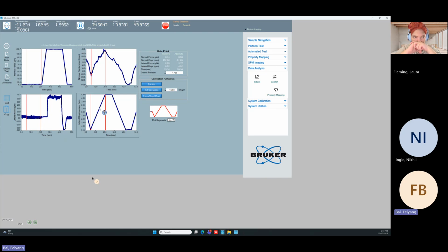So not too crack? So yeah, the reason I had this one moved in a little bit is, do you see how there's like this bump and then it goes down? I think that that's artificial and I want a better measurement. So I think that this is a more accurate representation of the sample tilt than going to the other side of this bump. So that's why I'm headed there. But yes, now you can hit tilt correction and it's going to make these 2 at the same lateral normal displacement or very close to it. So it's flattened this out. Now there is some bumps here. Aluminum is a weird sticky sample, so we're probably getting a little buildup. But you can see that that's what we've done here.